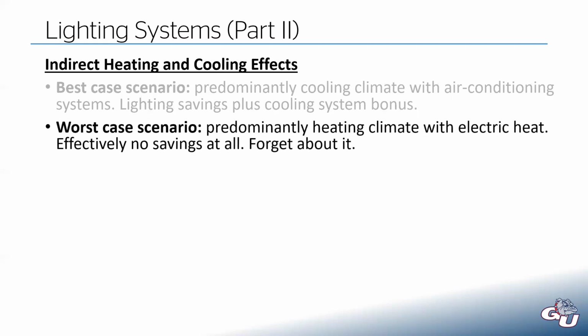But the worst case scenario would be a predominantly heating climate where your heating systems are running year round with electric resistance heat. Because every watt you save on the lighting side just has to be made up by the electric heater, which means you're effectively having no savings at all. So forget about it.